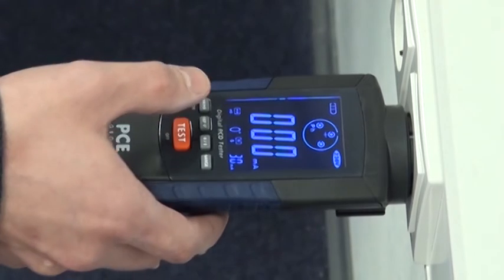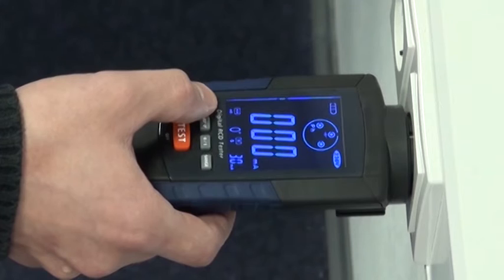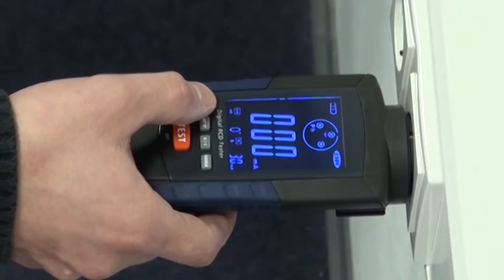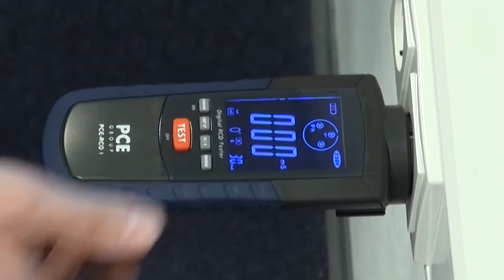The RCD1 is suitable for measuring the testing current at which the FI triggers. Furthermore, the triggering time can be measured in milliseconds.